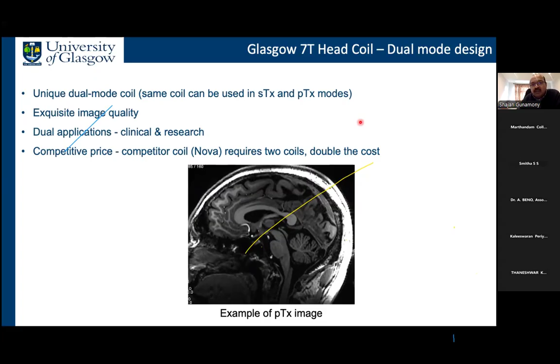And the other advantage, as I mentioned earlier, is claustrophobia. When you have a closed design, it's quite uncomfortable for the subject. As I explained already, we had to modify the antenna design using electromagnetic simulations to incorporate these 2 large cutouts. So we can then attach a lookout mirror for the patient to see the operator when they are getting scanned. Our coil is also more compact, it is shorter, about 220 to 230 millimeters, and it also weighs less, about 3.5 to 5 kilos. So that way, it's easier for the operator to handle the coil in a clinical environment, and it also optimizes the workflow.